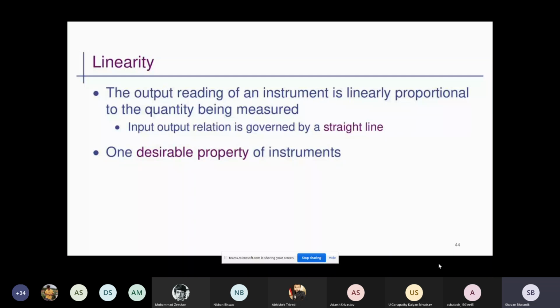If you linearize, you will always get a linearized expression. But wait, there is a linearization error associated with it, and that might be very high for some values. So you have to be very careful. Second point, as instruments are nowadays smart, they have their processing unit and memory. You can feed the exact nonlinear equation into the memory, get the input, and then display that measurement value. That is another approach.